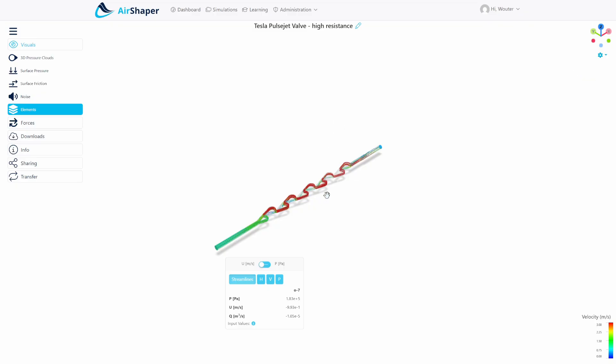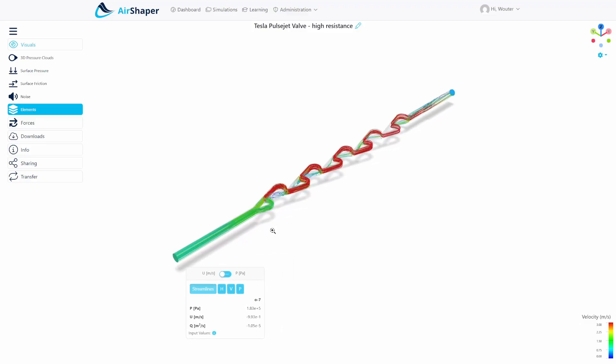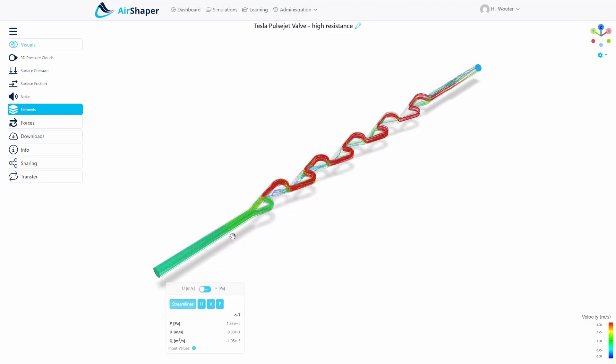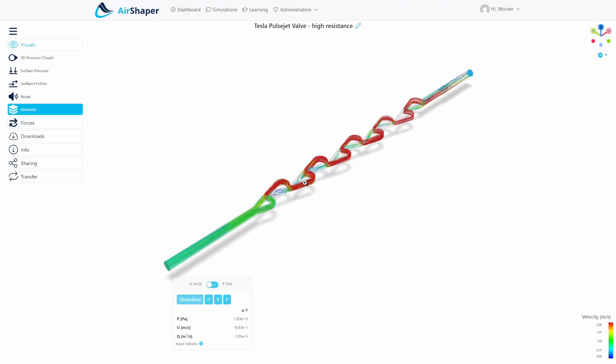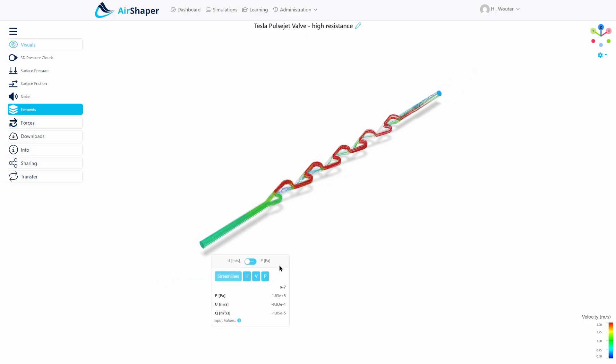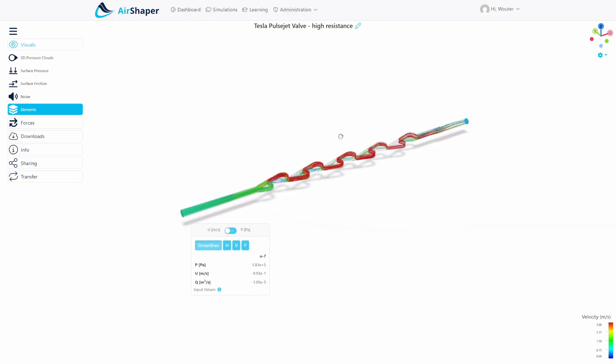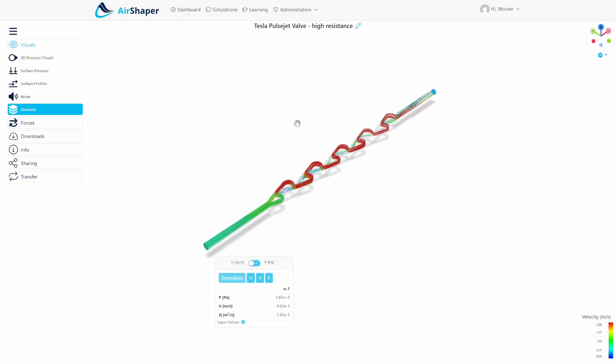If you look at the other simulation where the flow is going in the opposite direction starting here, you can see that it has to take this bend and then goes around. The flow through this part is being blocked by its own flow, and this really leads to a dramatically higher pressure drop of 183,000 Pascals, which is almost a factor of 6 between these two simulations.